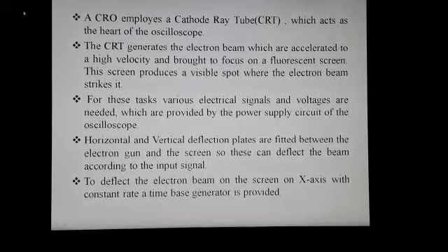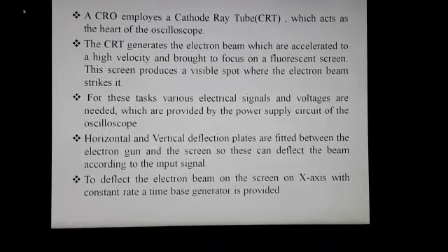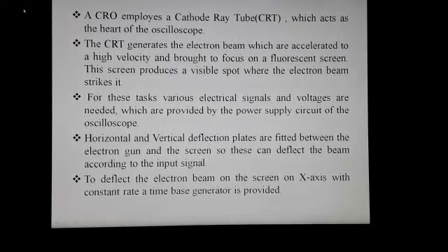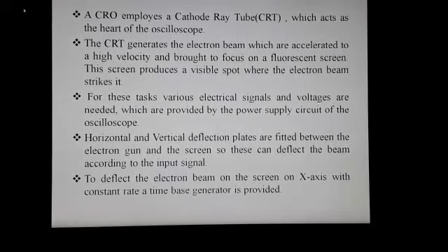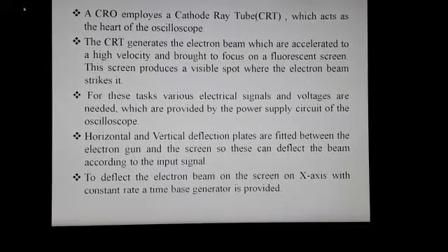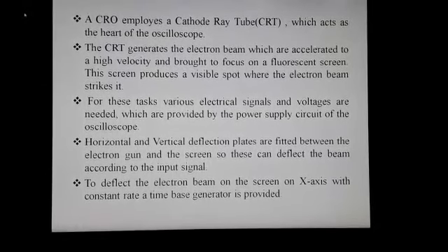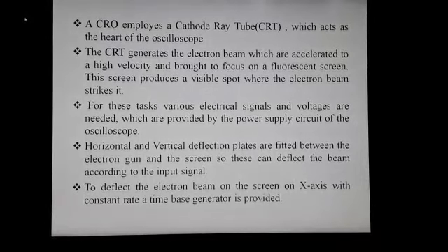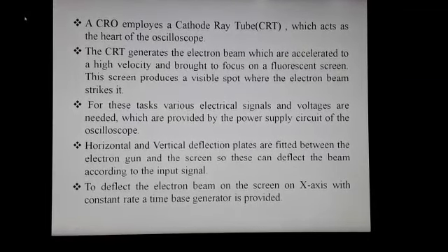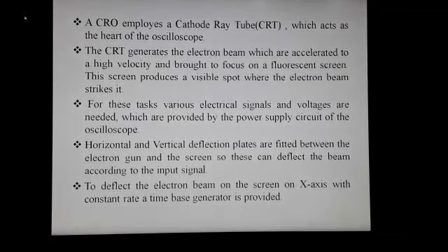The CRT generates an electron beam which is accelerated to a high velocity and brought to focus on a fluorescent screen. This screen produces a visual spot where the electron beam strikes it. Various electrical signals and voltages are needed, which are provided by the power supply circuit of the oscilloscope. The horizontal and vertical deflection plates are fitted between the electron gun and the screen so they can deflect the beam according to the input signal. To deflect the electron beam on the screen on the x-axis at a constant rate, a time base generator is provided.